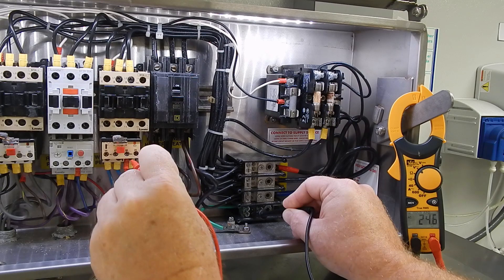When the machine is single phasing, this is the worst case of an unbalanced voltage condition. The motor draws more current from the remaining two supply lines at approximately twice the amount. The motor becomes overheated, and that damages and windings will shorten the life of the motor.